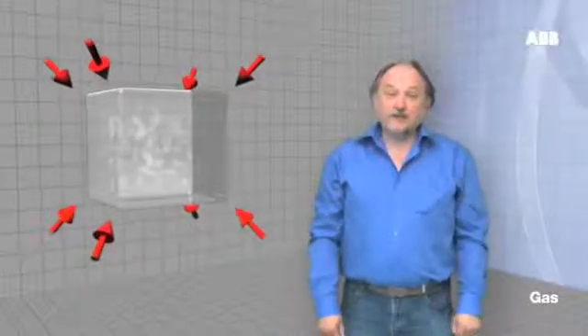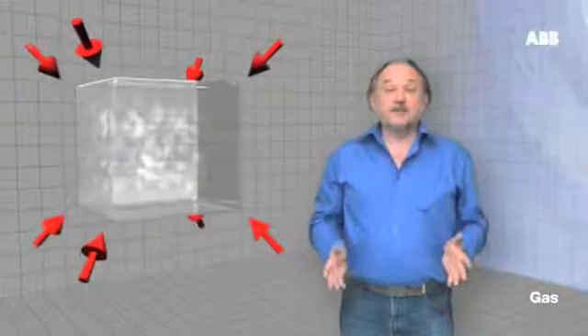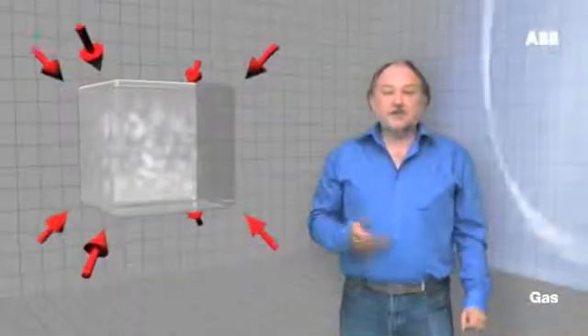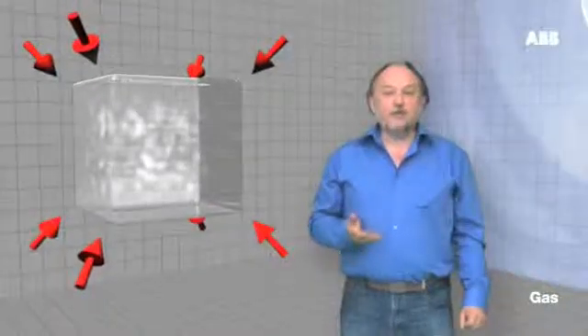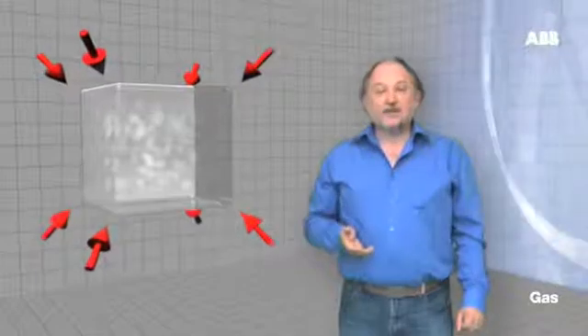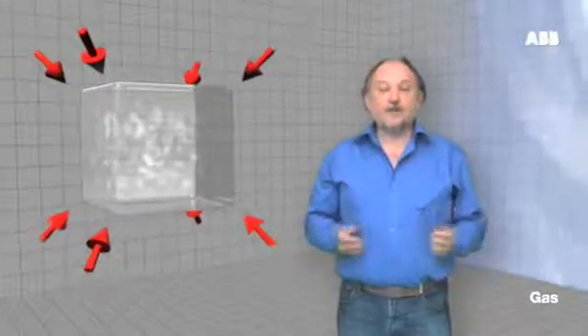Compressed air is not free. It costs your process as much as the energy needed to compress it in the first place. If you measure air flow with a mass meter, you have an accurate and stable measurement of how much compressed air you're using and distributing, offering better accuracy and control possibilities for compressed air usage and generation around your plant.